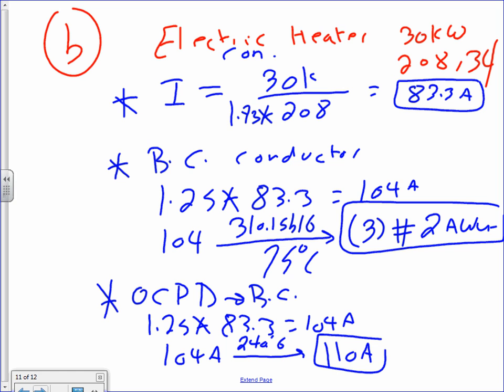The last load, and I'm picking these loads specifically because they represent loads that you guys have. Take this: I have an electric heater, 30 kW, 3-phase, and I need to size it. Now remember, these are dedicated circuits for equipment. Here's how we do it. Take the amps. For the conductors, 1.25 gets you to number 2, and the overcurrent device, 1.25 gets you 110. For heaters, because they're resistive load, we use the kW to find the amps, and from the amps we multiply by 1.25, and we size both the conductors as well as the overcurrent device from the same 1.25 times the full load current of that piece of equipment.